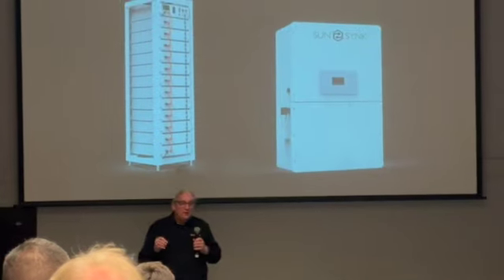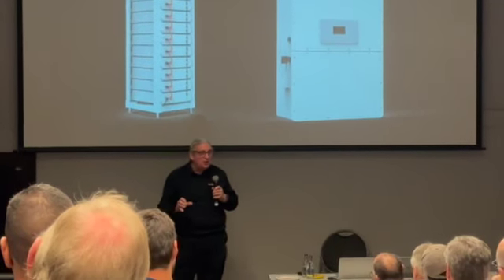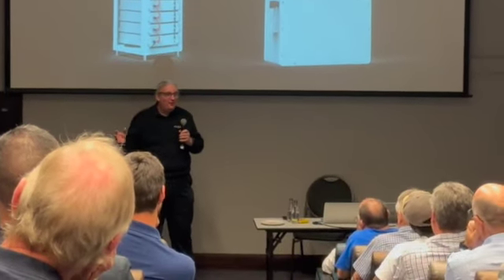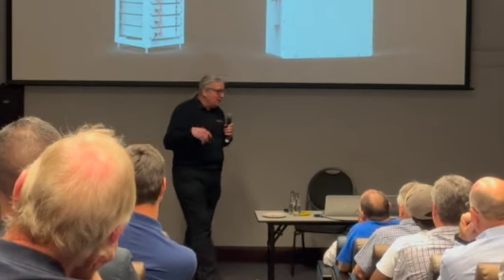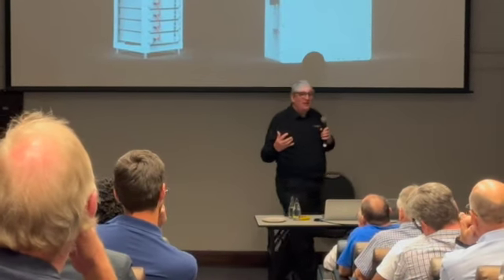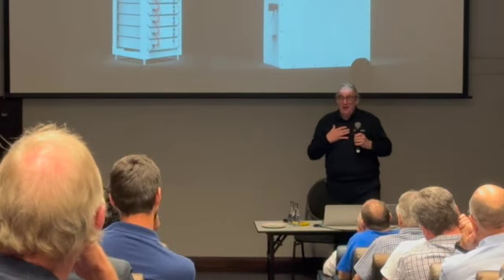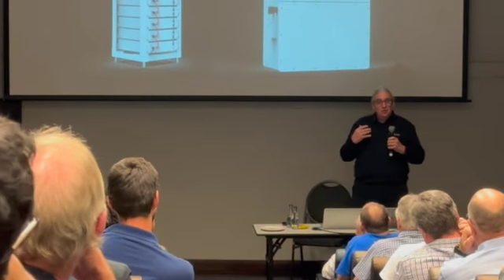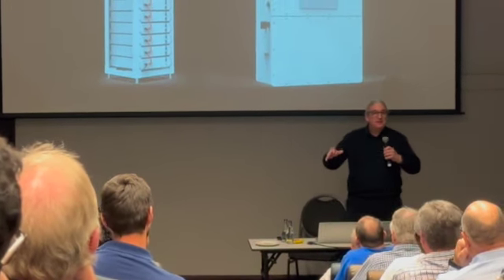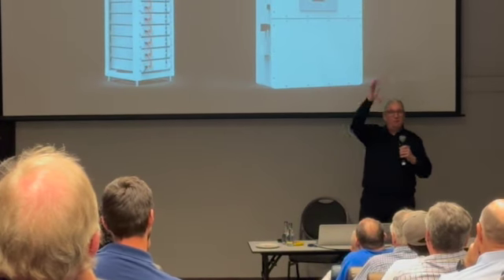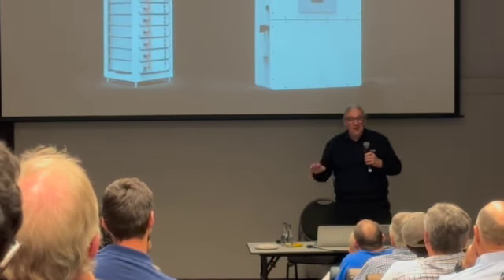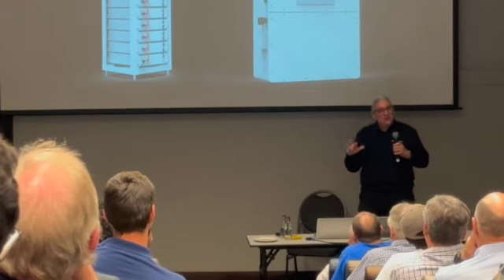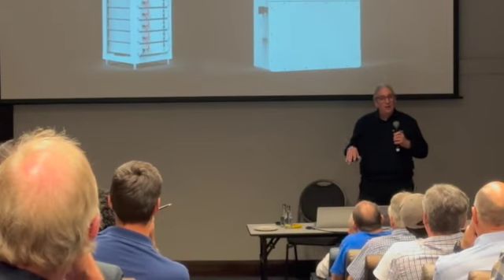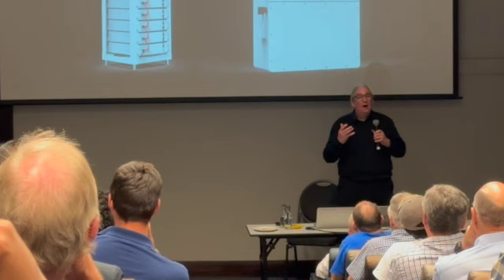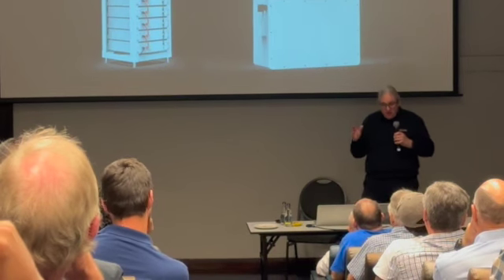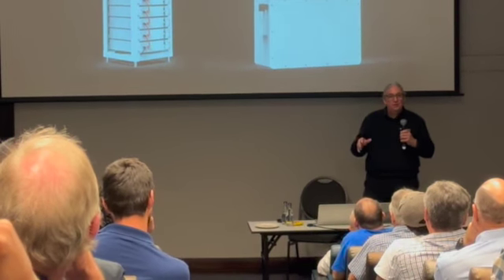When you're setting your charge and discharge currents, it's only a twelfth of what you'd set before. It might sound obvious, but I fell for it and it caused a trip. So just start off low. If you're setting the system up, take your charge and discharge and put them on 1 amp, really low, or 10 amps, 6 amps, just keep it relatively low. 1 amp is already 600 watts, and then bring it up gradually. It's a huge difference from the 48 volt system.